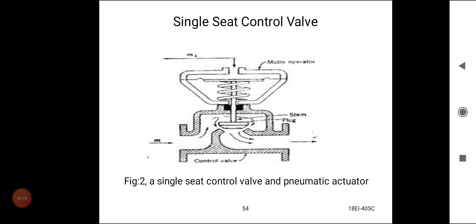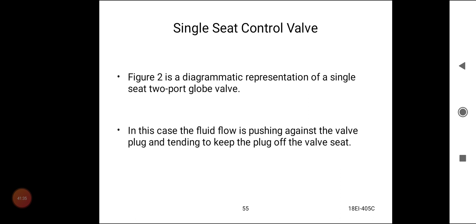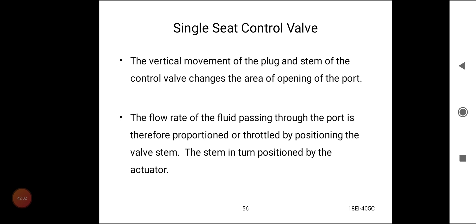Figure 2 is a diagrammatic representation of a single seat 2-port globe valve. In this case, the fluid flow is pushing against the valve plug and tending to keep the plug off the valve seat. The vertical movement of the plug and stem changes the area of the port opening. The flow rate through the port is therefore proportioned and throttled by positioning the valve stem. The stem in turn is positioned by the actuator.